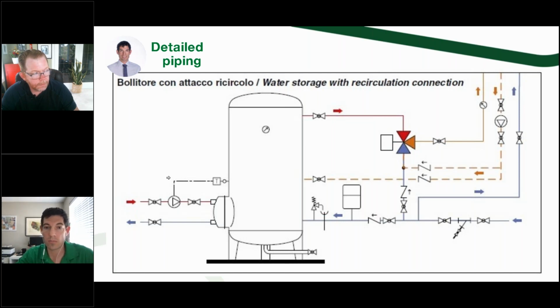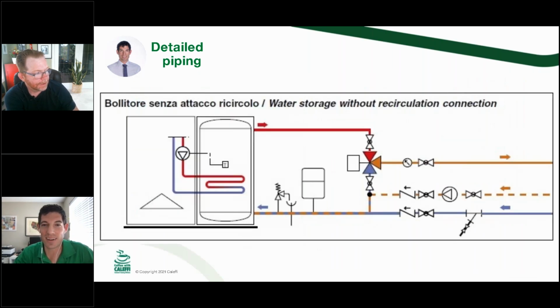You don't need the globe valves for balancing because it will close off that hot completely. So that's something to keep in mind for just the overall installed cost of that. And there is a much more concise version of what I just said that Cody Mack did at our shop, that's on our YouTube channel. That's ways to prevent recirc creep, that goes through that diagram a little bit better. He's been around that diagram longer than I have.